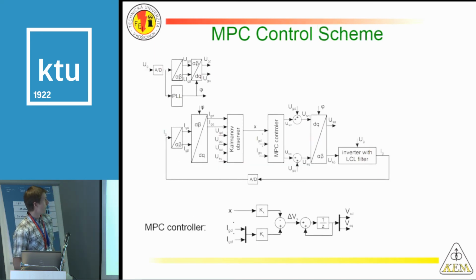That MPC controller was then applied to the inverter with the LCL filter. Here is the structure of the control system. I have an inverter where I measure just the grid current. There are three variables, but I measure just one of them, the grid current. The system is also influenced by the grid voltage.